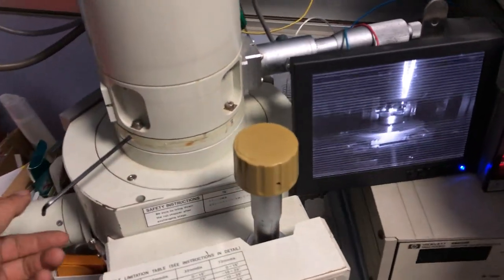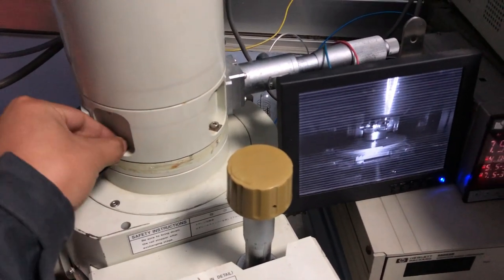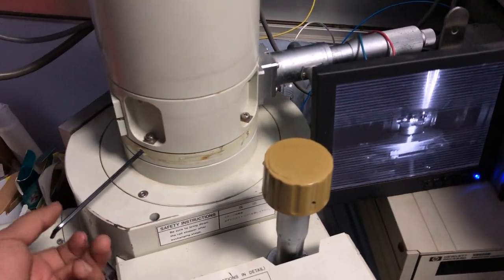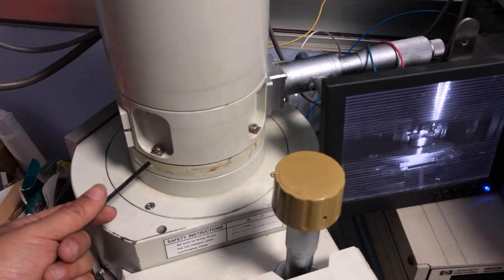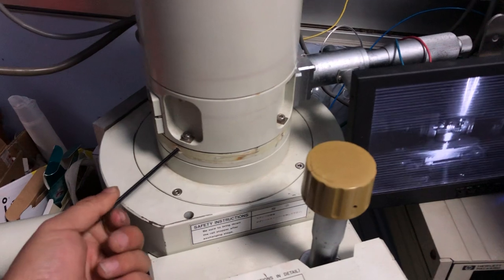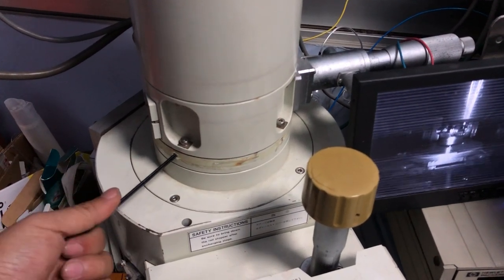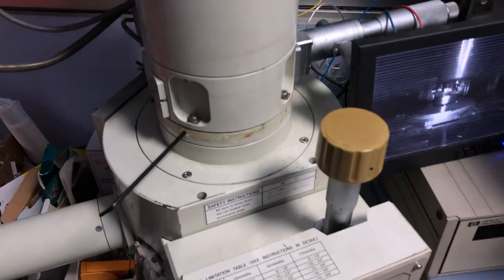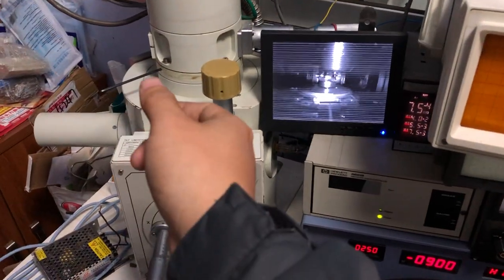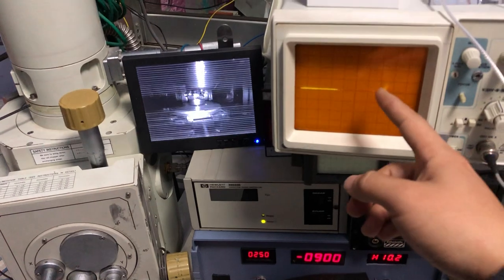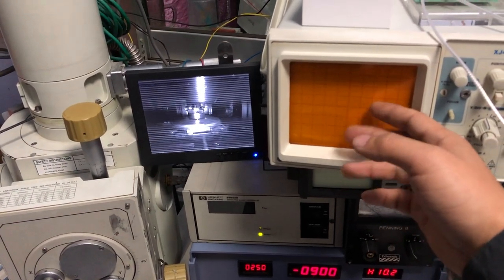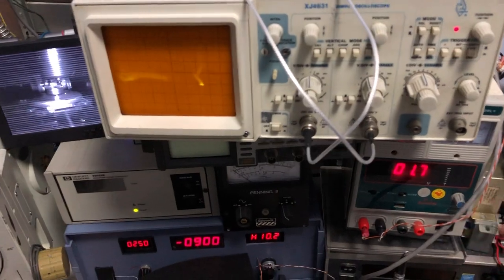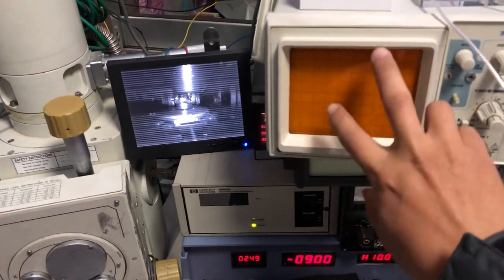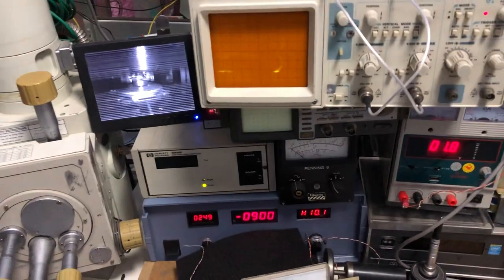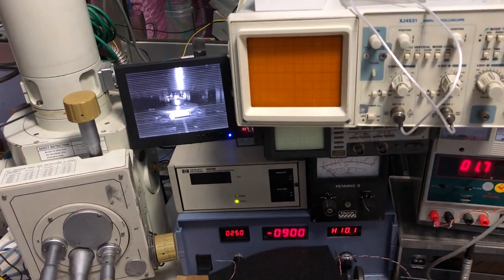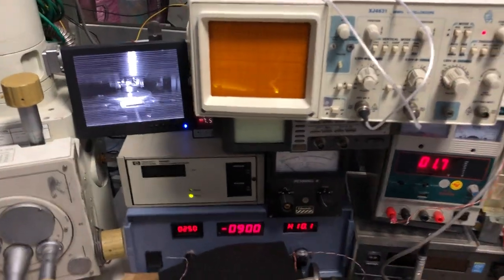So today what I do is loosen these screws a little bit and twist these screws with this driver a little bit. And when I turn this driver a little bit, I'm watching this screen and adjusting the focus to see whether the image still shifts. And now we can see basically a pretty clear image.